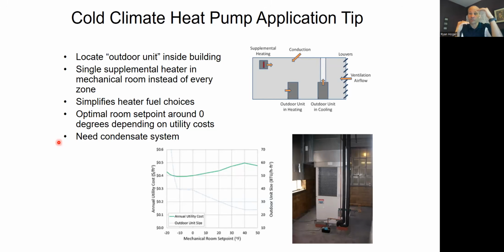I don't want to size the whole thing for heating because then I'm grossly oversized for cooling. So usually I size for cooling and somebody else helps me out on heating, just like we talked about on the split systems and stuff before. So now I got all these VRF units all over the place, and now I have to add heat to all those rooms as well. Two ways to do that.